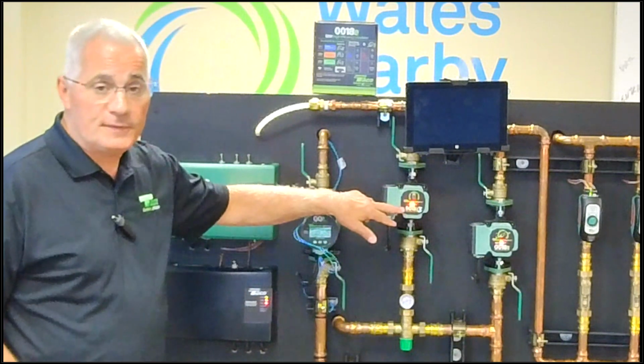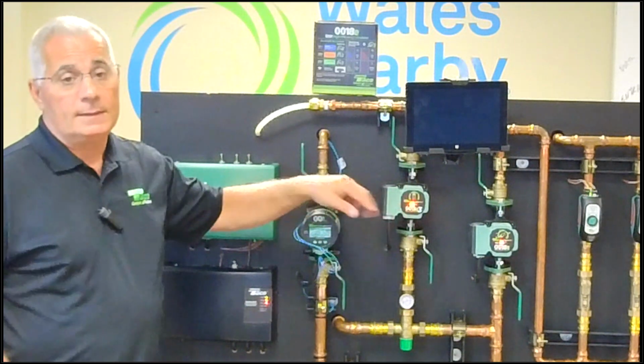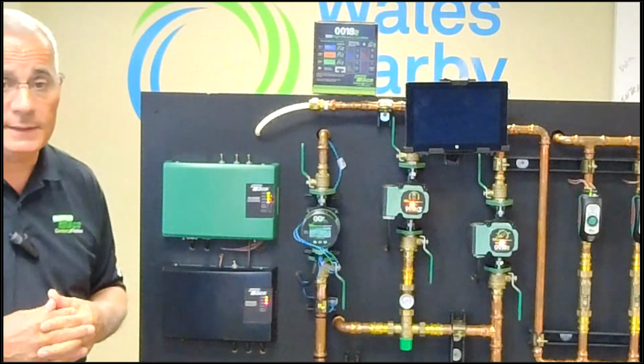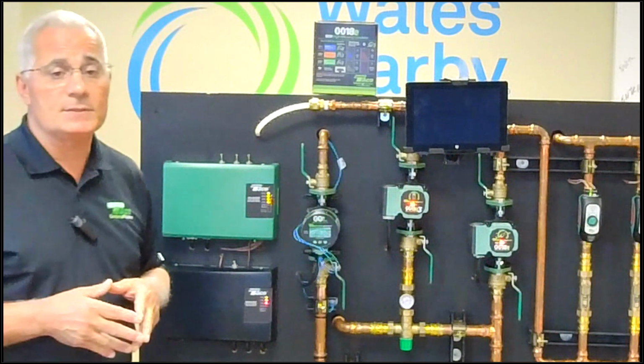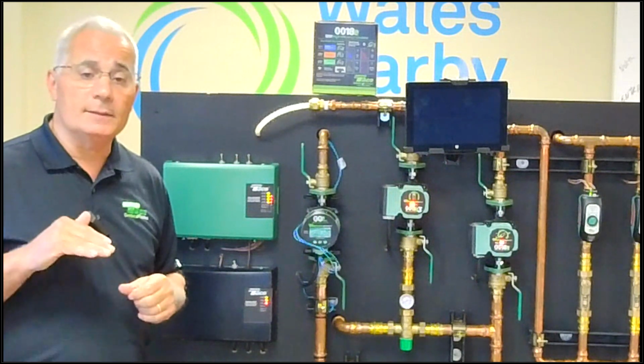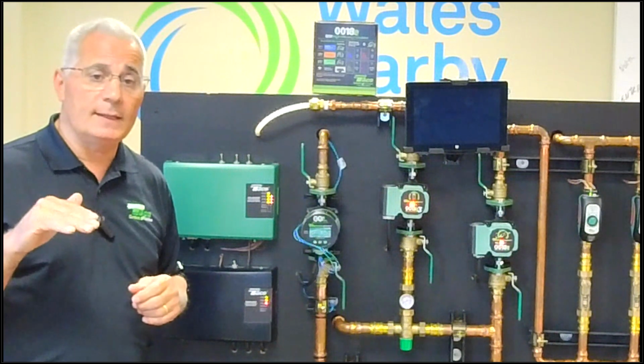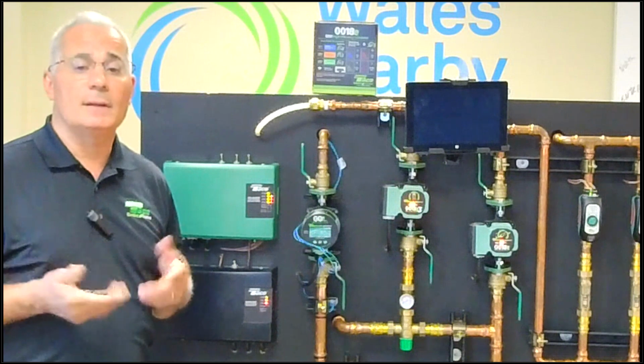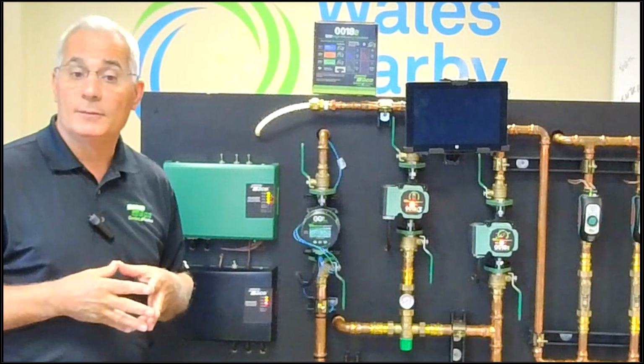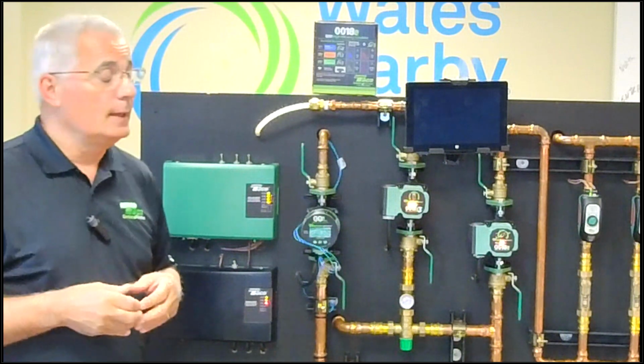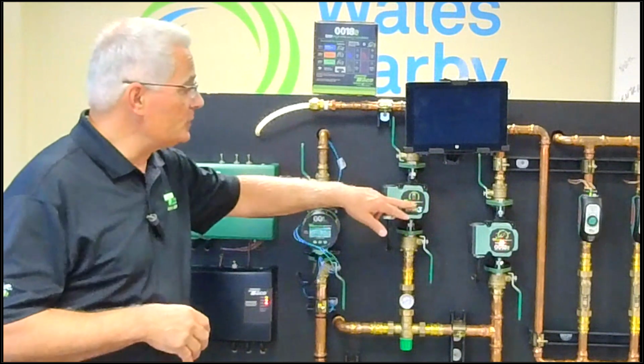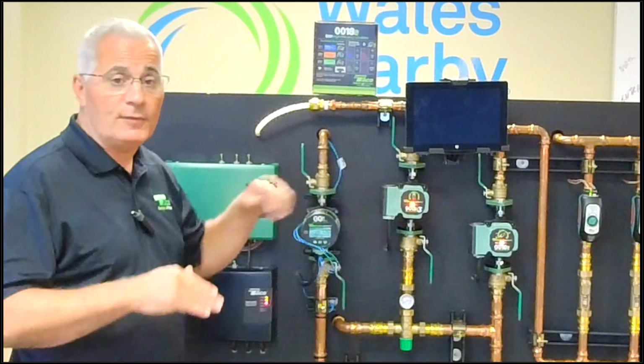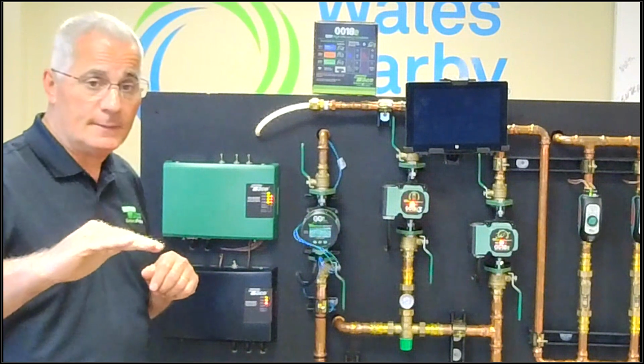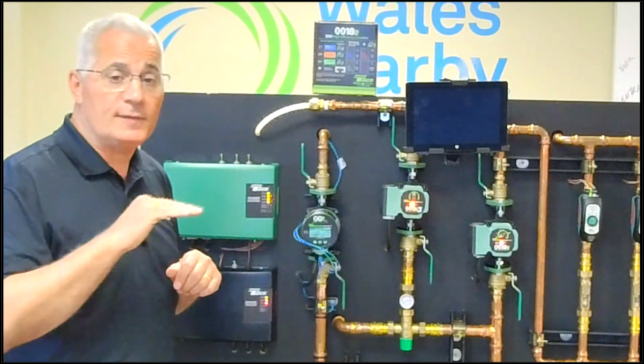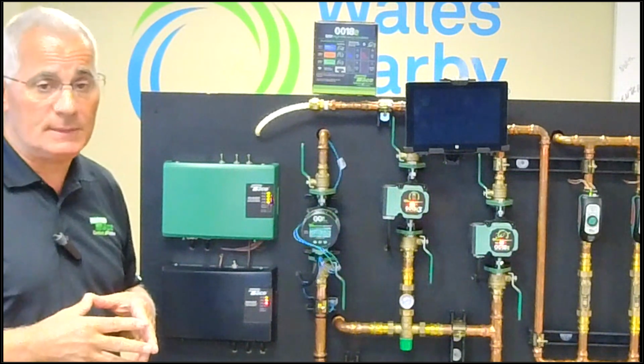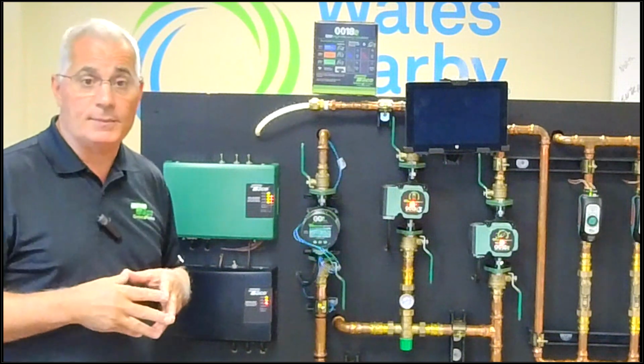This is the 0015E3. This is a variable speed circulator, and we've talked about this many times, and I will vary my speed on the low setting and on the medium setting, and when I get to the high setting, then I'm at 100% speed, which would be 44 watts. As zones open and close on the low setting, I will follow 5 feet of head. It'll run along 5 feet of head out to 12 GPM, or 120,000 BTUs.